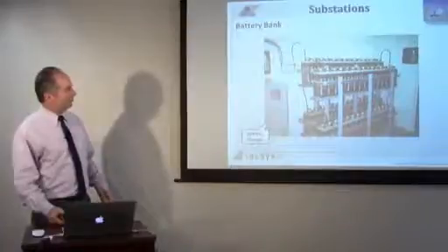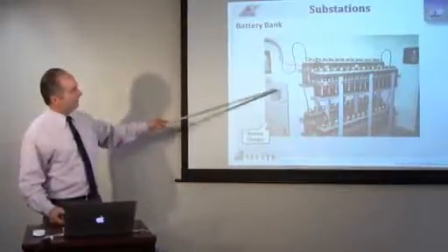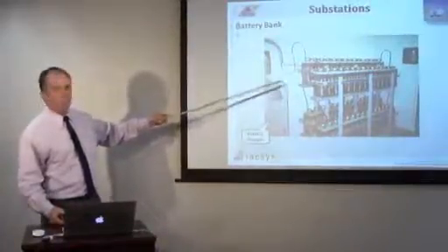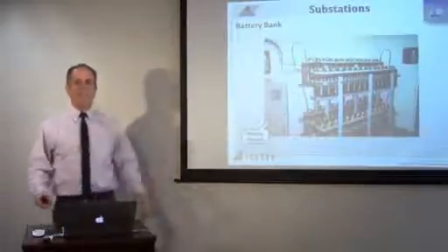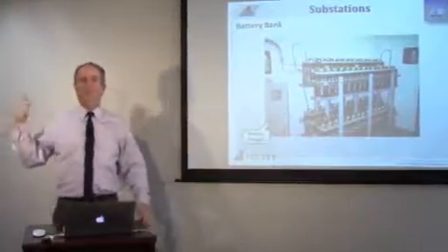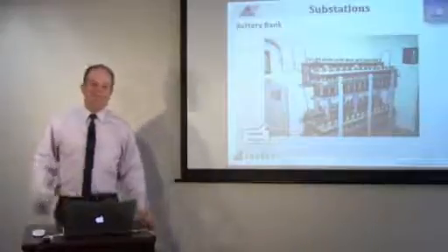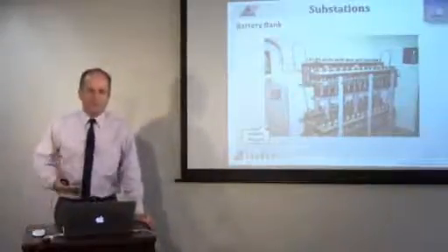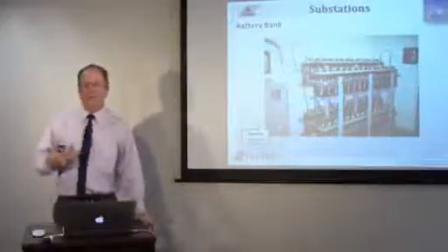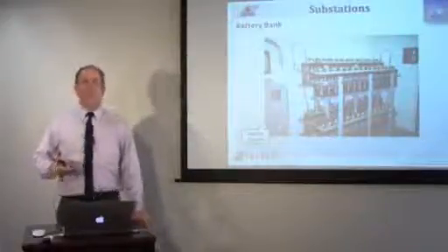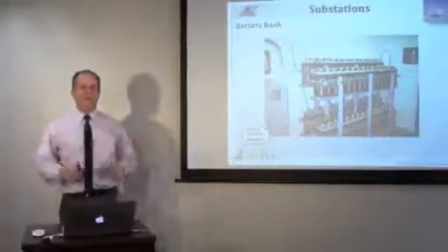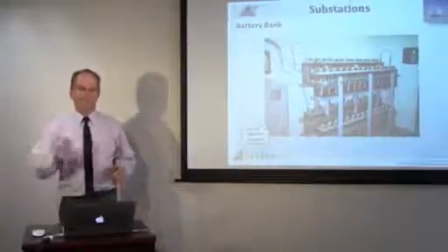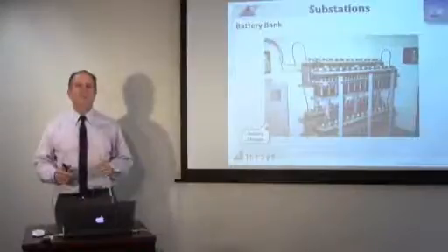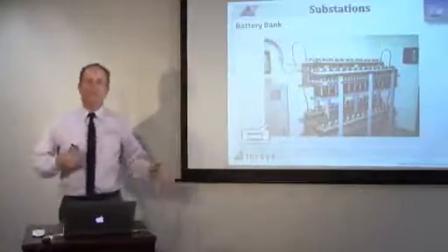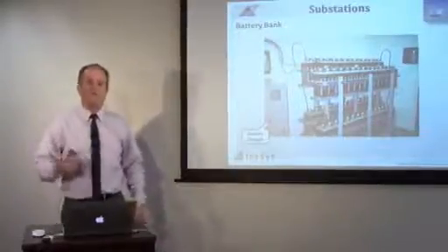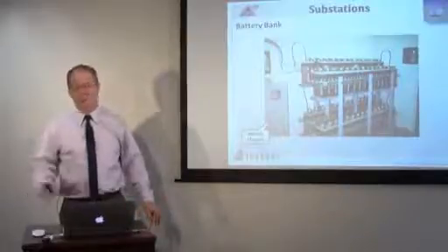This battery bank is used to power the relays and the telecommunications equipment, what have you, because that equipment cannot be on AC power. If the AC power goes out, you can't control the equipment. These are usually about 125 to 130 volt DC battery banks. When all the equipment, the protective relay, telecommunications, all the control center equipment, is operating on batteries and the AC power goes out, you can still operate, you can still control things via the batteries. When the batteries go out, then you're dead in the water.